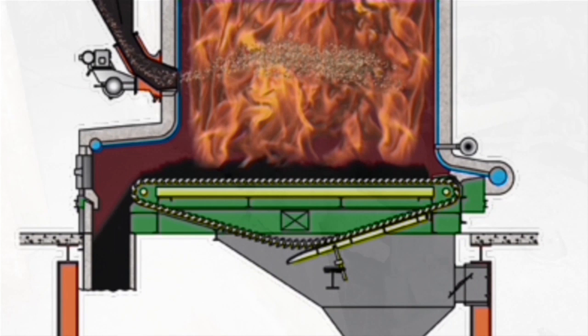Welcome to boiler number five. You might be able to see some of these doors where the operators could check the flame on the grate. This is the Detroit Rotograte Stoker — the spreader stoker flings the coal onto the grate and the grate slowly moves towards us, so there's fire on the grate and fire in suspension. From the grate, the ash is conveyed to the ash pit.